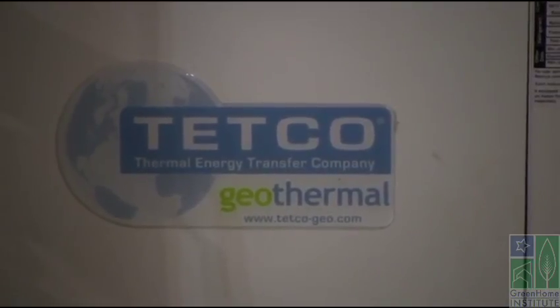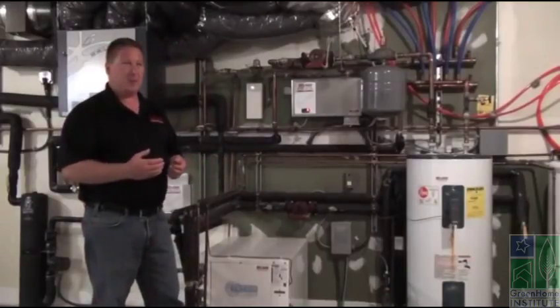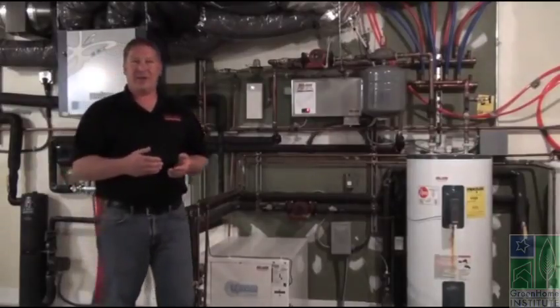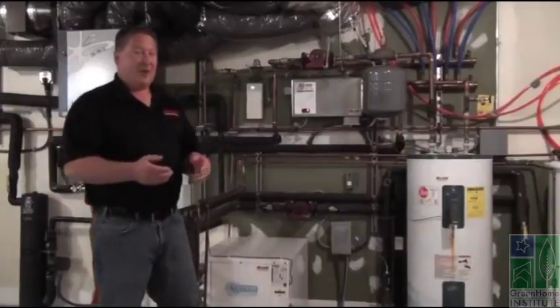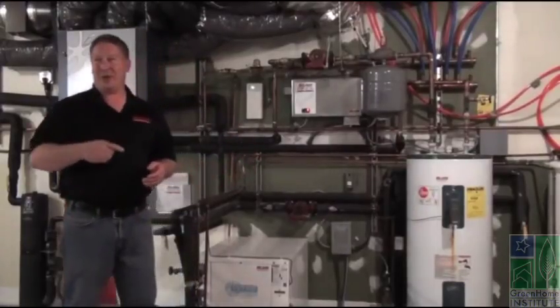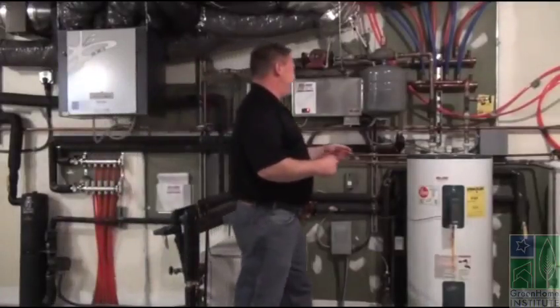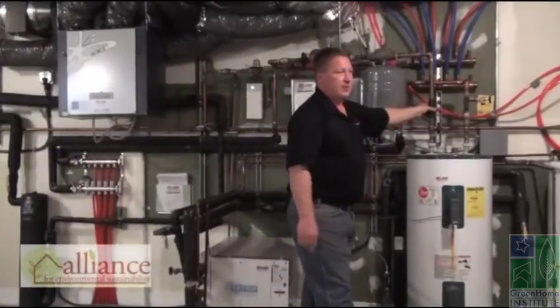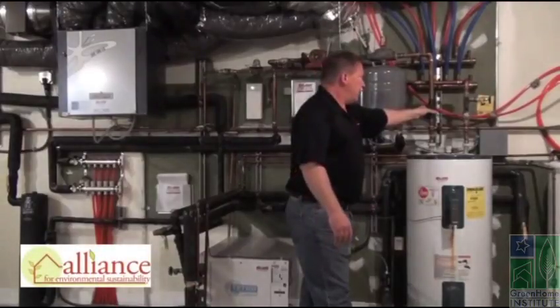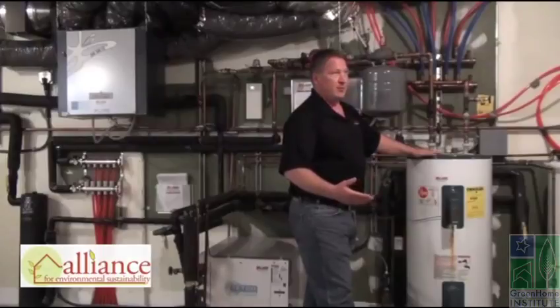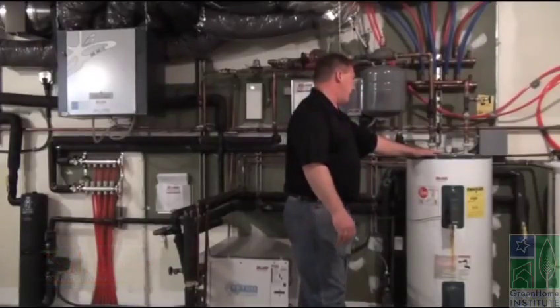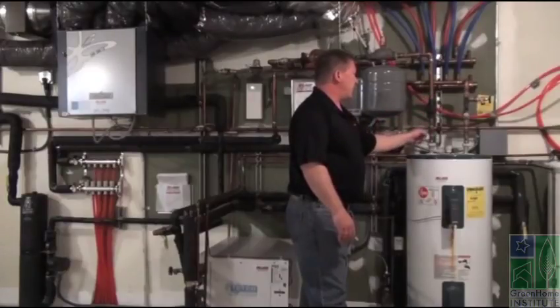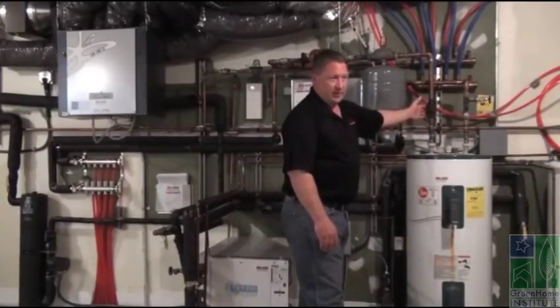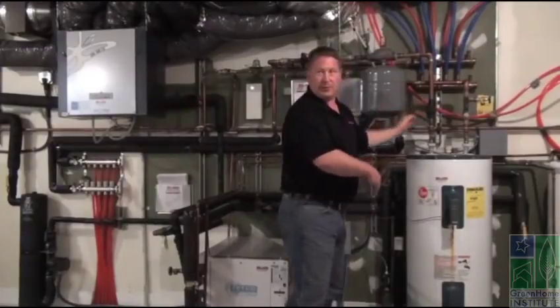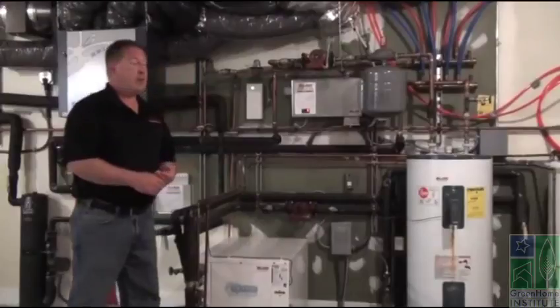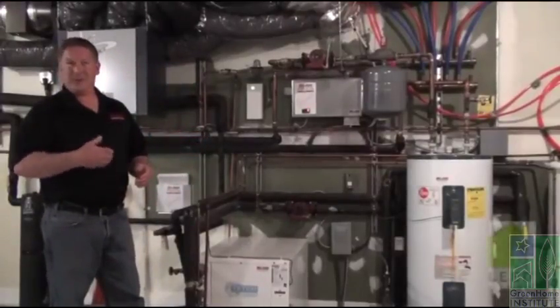This geothermal system can make water as cold, or fairly as cold as I want it to, but the problem with water getting cold is there's a certain point that it changes state from a liquid to a solid. And we can't pump solids around in pipes very well. So there's another thermostat that is functioning only during the cooling mode when it's trying to cool the house, that will limit this water to a temperature of about 55 degrees. Can't get any colder than that. So when it's monitoring the temperature on this pipe, when the water is circulating through this pipe, it's sensing the temperature here, and if the temperature gets to 55 degrees, then it will shut off the compressor in the geothermal unit, which is fine.